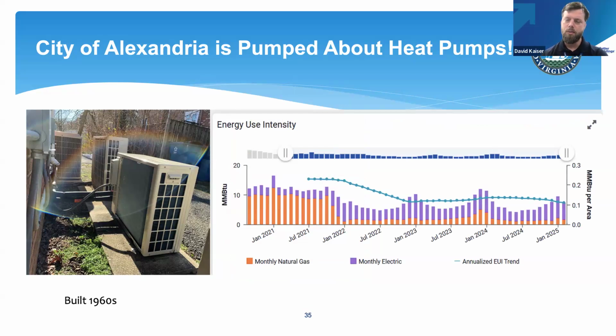It was an initial gas direct fired, with a chimney flue atmospheric boiler, and we got about a 50% energy use reduction at the facility, roughly, for installing that heat pump hot water system because it was so efficient. Next, please.